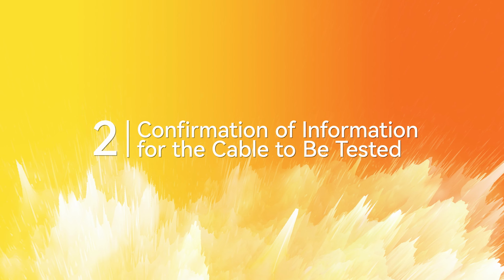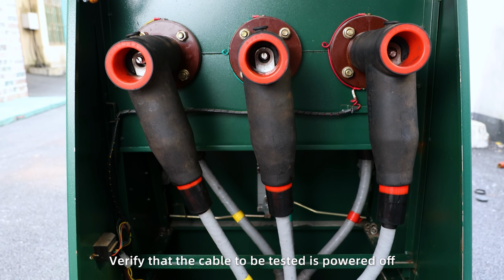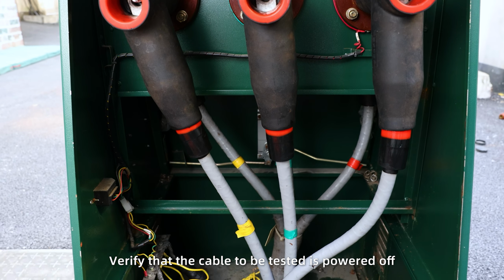2. Confirmation of information for the cable to be tested. Verify that the cable to be tested is powered off. Ensure all 3-phase conductors at both ends are isolated and floating.